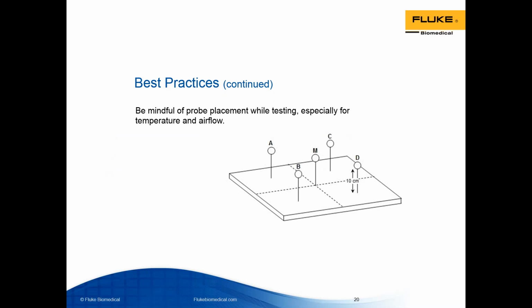So the probe placement, and the reason why I placed this question in this webinar is because the placement of probes when you're testing parameters, especially temperature and airflow, are common misunderstandings when testing and performing the preventative maintenance for infant incubators. So the sensors for all parameters, including temperature, humidity, the airflow, and the sound, should be 10 centimeters above the mattress, which is approximately the height of an infant when laying flat on the mattress of the incubator.